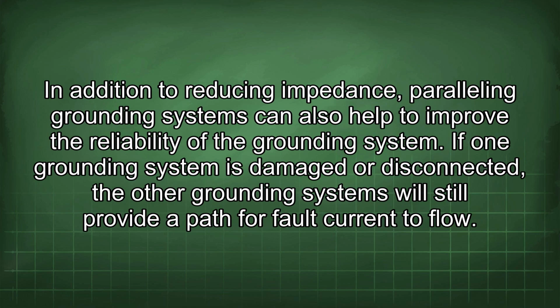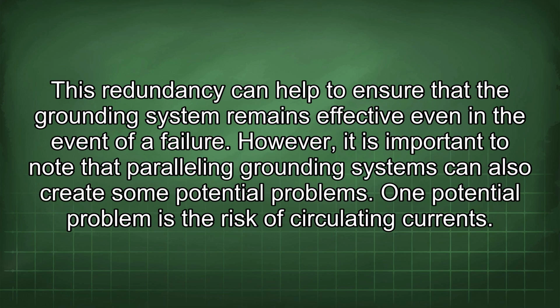In addition to reducing impedance, paralleling grounding systems can also help to improve the reliability of the grounding system. If one grounding system is damaged or disconnected, the other grounding systems will still provide a path for fault current to flow. This redundancy can help to ensure that the grounding system remains effective even in the event of a failure.